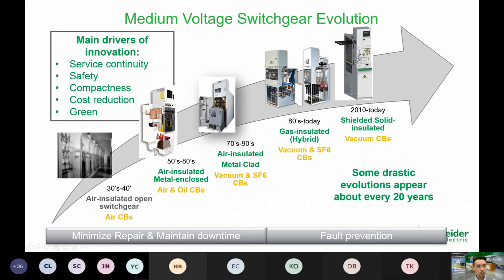Then it goes into some innovation in design, which we call the evolutions. There are some key factors that take place, right? The designers are constantly looking into how to redesign it to give better service continuity, better safety, a much smaller footprint, and how to make it more cost effective and also greener. Based on all these factors, you can see it start to evolve along the way from the 50s to the 80s, where it still revolves around air insulated switchgear. But starting especially from the 80s to the 90s, that's where gas insulated switchgear starts to come into the picture.